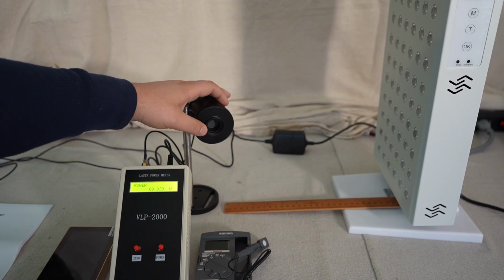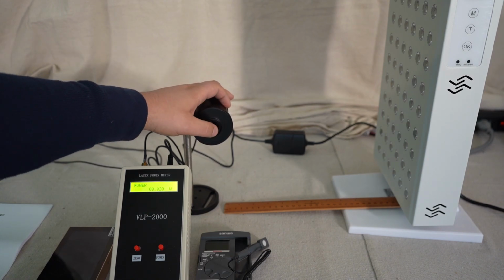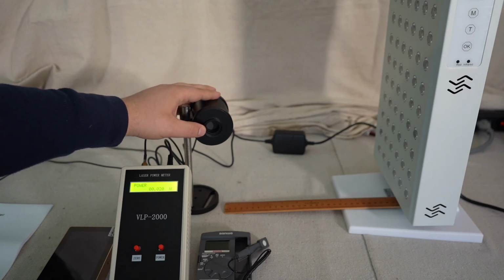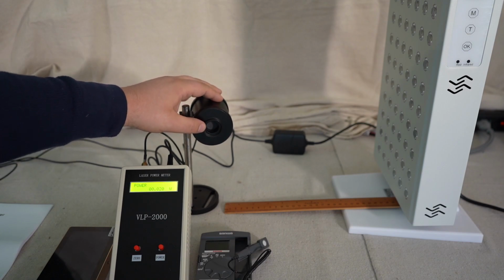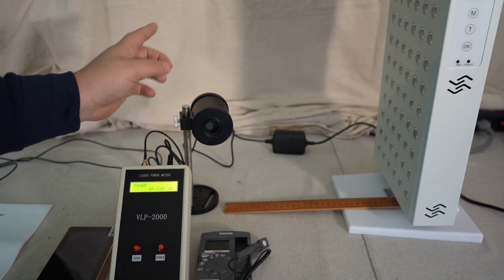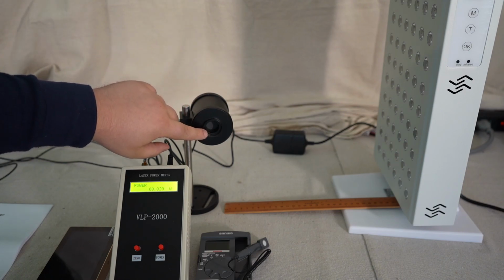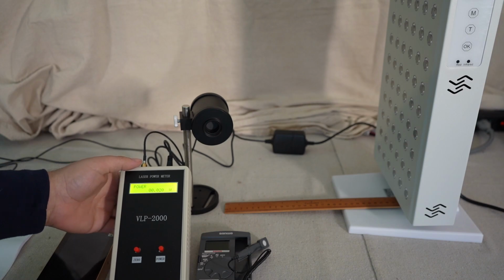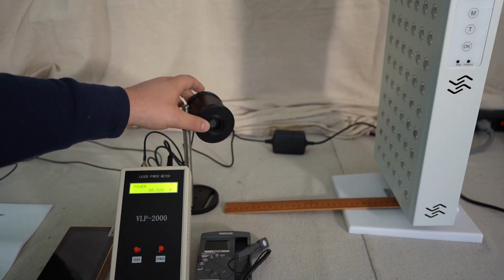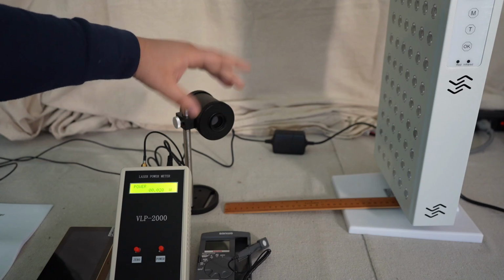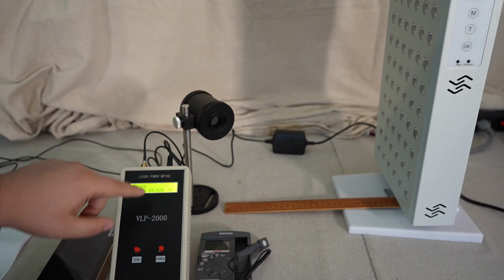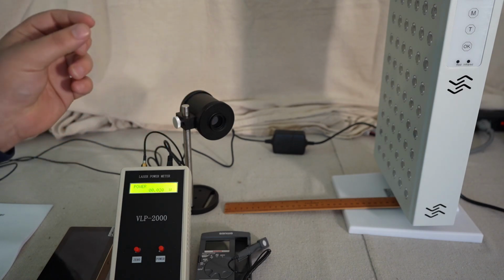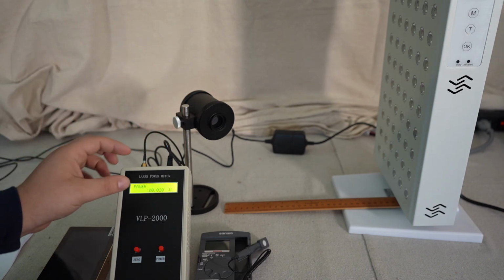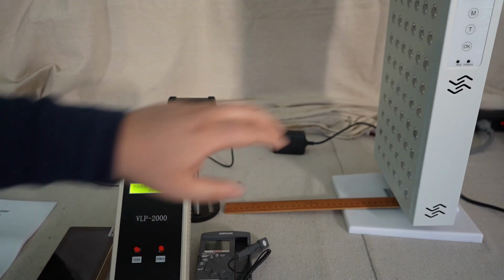And so this sensor is 2 centimeters in diameter. That makes our area calculation really easy because we are going to do pi r squared, where r is going to be 1. So 1 squared is just 1. So really we're just dividing this number, the milliwatts, by pi, which is 3.14159. So it's very simple. We just divide this number by pi, and that gives us our intensity, our milliwatts per centimeter squared. So it should be super simple. We've got this set up. We're going to do both red and near infrared.